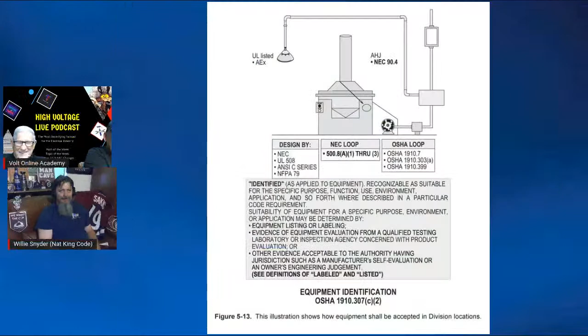There you go. Well, this illustration is basically with OSHA 1910.307C2, and you can see to the right of the illustration, right below the equipment, the OSHA loop there. I won't go over it, but that is the actual OSHA loop when it deals with intrinsically safe and non-incendive type circuitry. If you're going to approve this equipment as an inspector, for example, or even as a designer or installer...